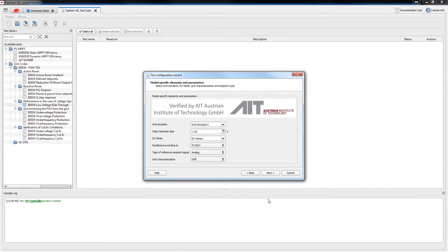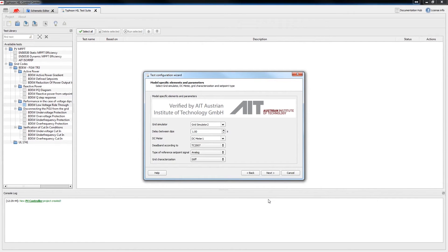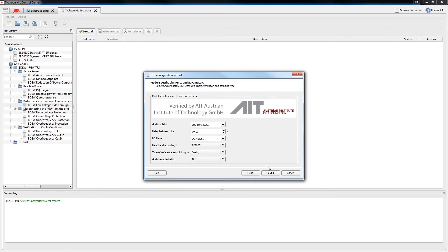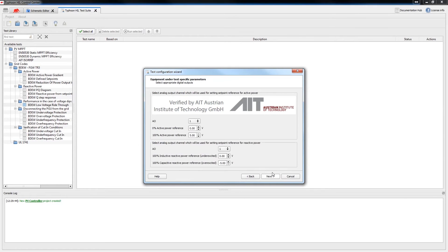The grid simulator and DC meter elements are included in our power stage model and will be simulated on the HIL with a 1 microsecond update rate. Let's set the delay between dips, choose the dead band according to TC 2007 because we are testing a PV controller, type of reference setpoint signal, and stiff grid characterization.